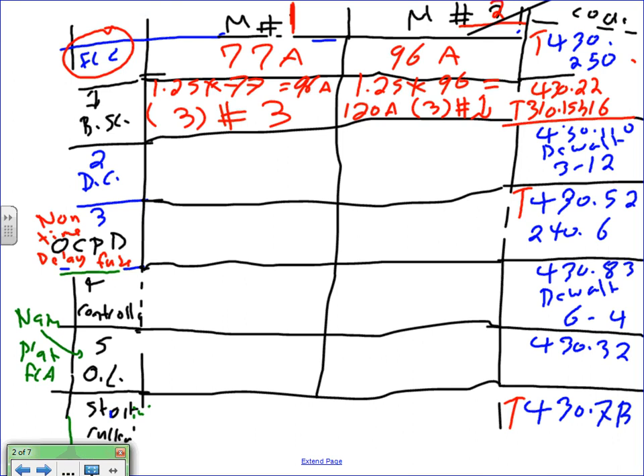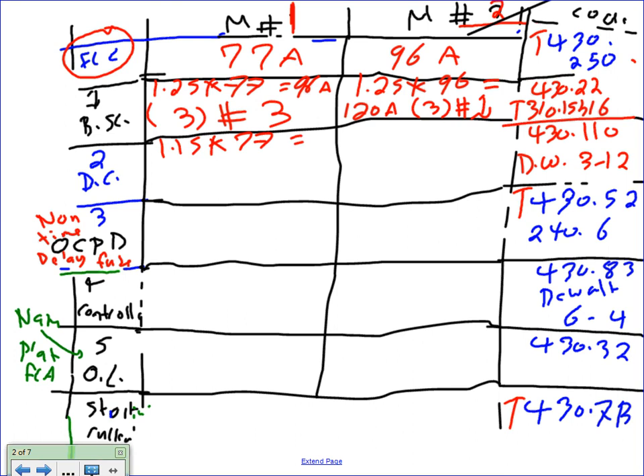If you guys go to article 430.110, this is, believe it or not, 430.110. You need to find the actual size. So we all know you talk about 1.15 times 77. If you guys did this one, you end up with 89 amps, and that will get you, from the horsepower table, a 100 amp. And then you go to the second one, 1.15 multiplied by 96.